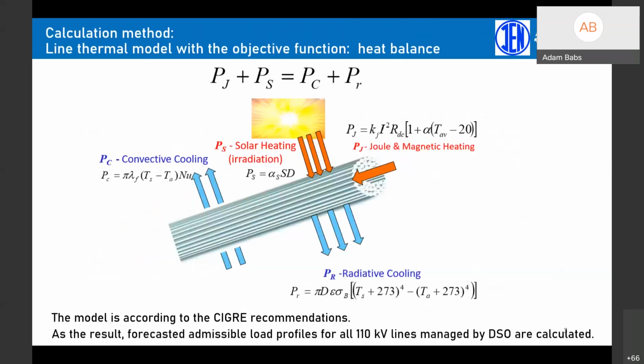The permissible line current is calculated using the heat balance equation, with temperature being the limiting value. This temperature is responsible for the permissible sag of the wire and thus for maintaining the normative distance between the wire and the ground in each span of the line. In normal cases for 110 kV, this distance to the ground is 5.74 meters.